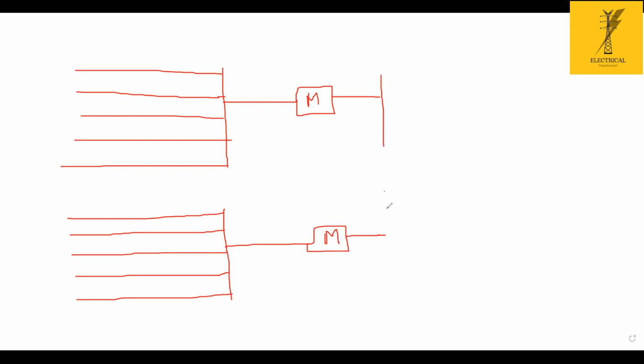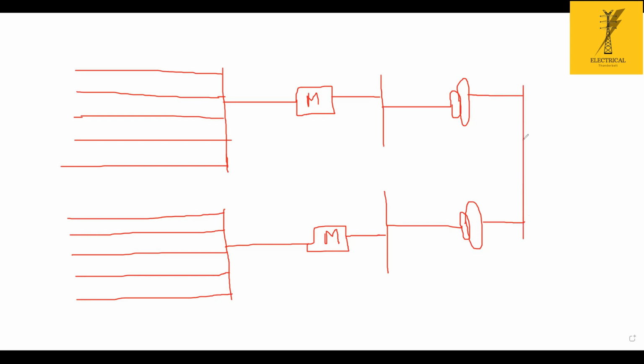I am developing the single line diagram in this way because in the 33 kV we decided on single bus bar with sectionalizer, right? So I am making this here, and from here connecting to the transformers. And from this transformer it is connecting to again a metering. Meter in the sense both, I already told you both. And this is connecting to the double bus bar configuration.